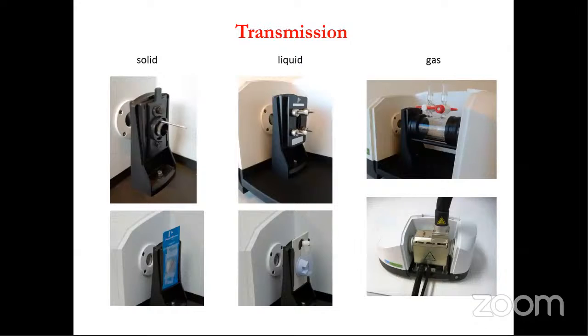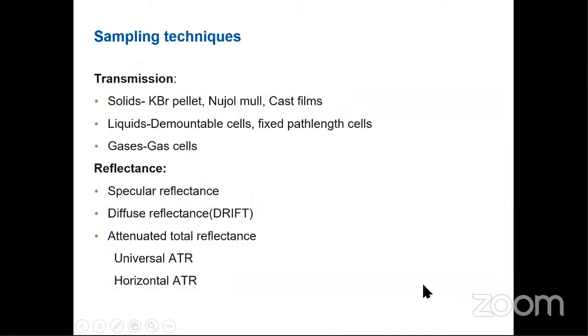These are the modules that transmission works with. They are basically probes: a solid probe, a liquid probe, and a gas probe. There is also a pouch, which is a type of probe, and it is a continuous process where the gas is coming and going. For sampling techniques in transmission, for solids we have the KBr pellet, Nujol mull, and cast film. For liquids, we have a demountable cell which we can demount and fill with the liquid. For gases, we have a gas cell chamber. For reflectance, we have specular reflectance, diffuse reflectance, and ATR. ATR is a universal ATR or a horizontal ATR.